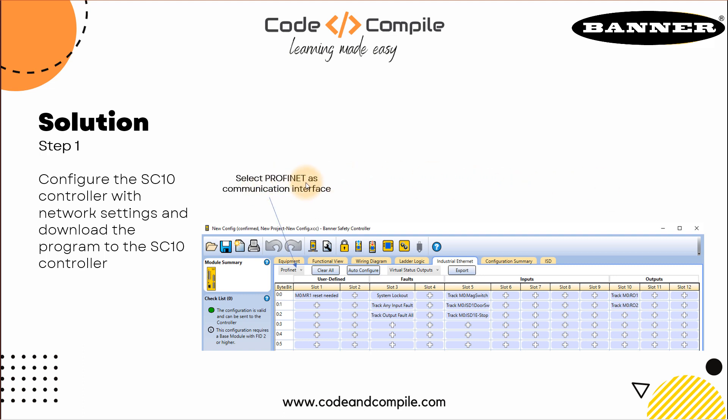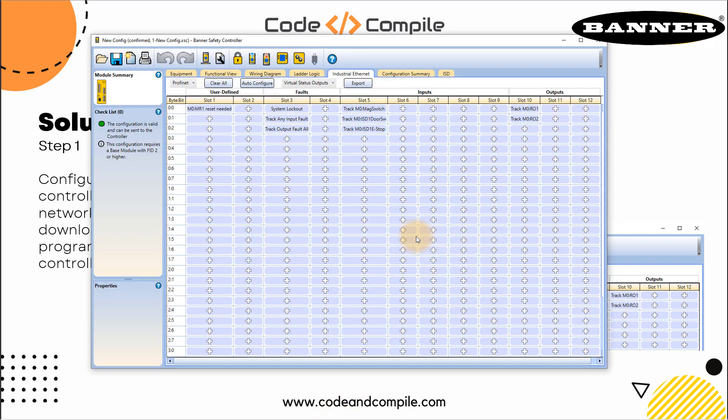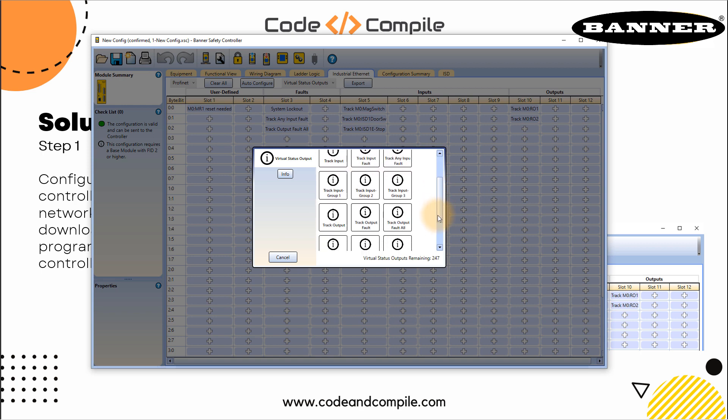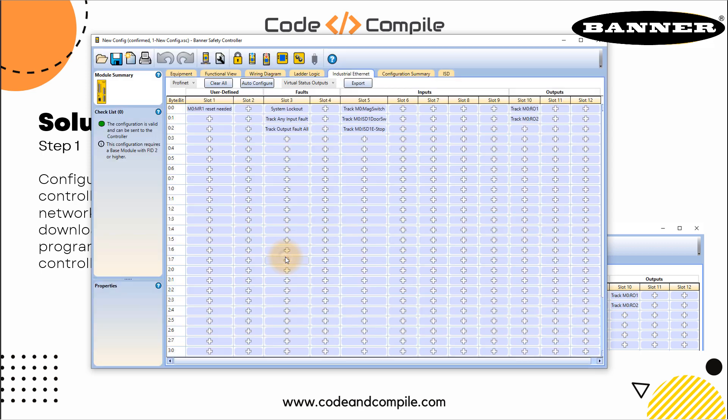We have configured select PROFINET as communication interface, use auto configure. This is very important. Once we are communicating via PROFINET, we need to know which data you want to read and write. You can click on the empty slot and define what you want to send via PROFINET. For example, track input, track input fault, track any input fault - you can select from any of these options. If you're not sure what you want to select, or if you just want to make a trial, you can click on auto configure. When you do that, the software will automatically assign some slots with some functions.